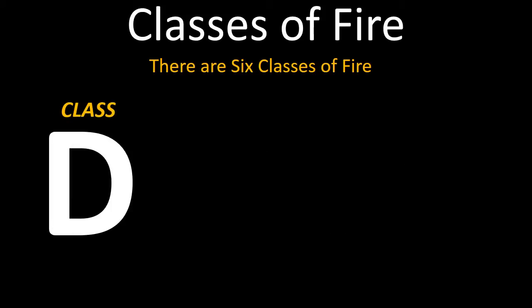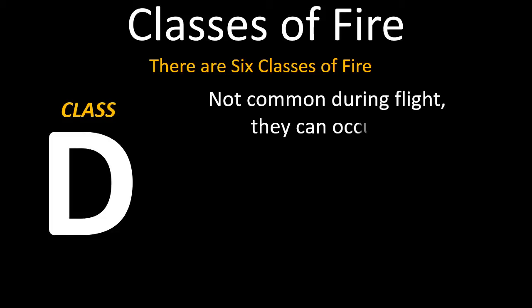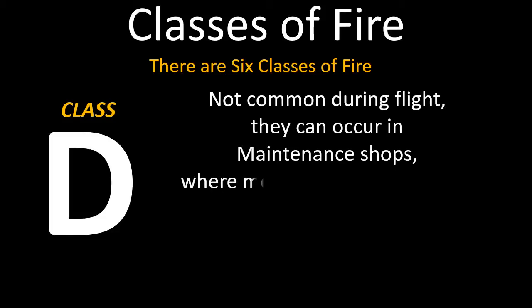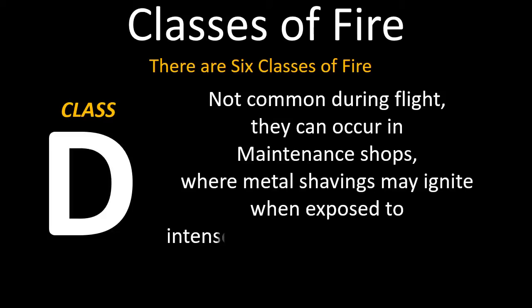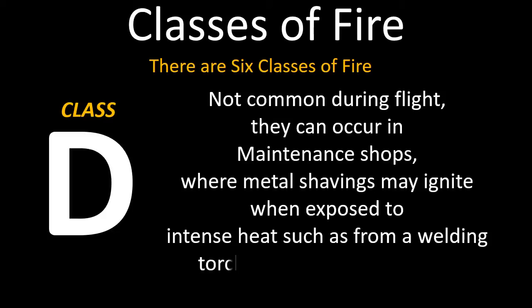Class D fire involves burning metals such as magnesium and are difficult to extinguish. Using the wrong type of extinguishing agent with these may not only be ineffective but may even cause the fire to spread. Although these types of fires are not common in aircraft during flight, they can occur in maintenance shops where metal shavings may ignite when exposed to intense heat, such as from a welding torch or high voltage source.